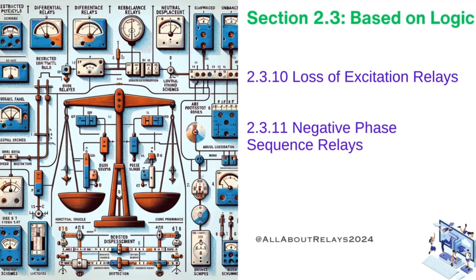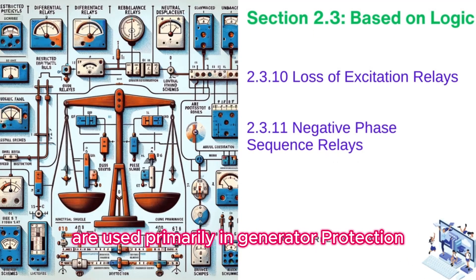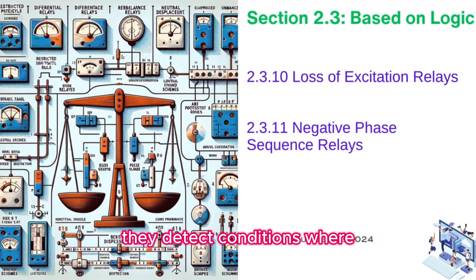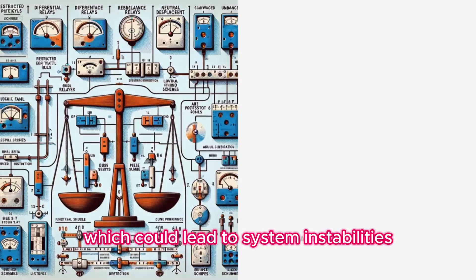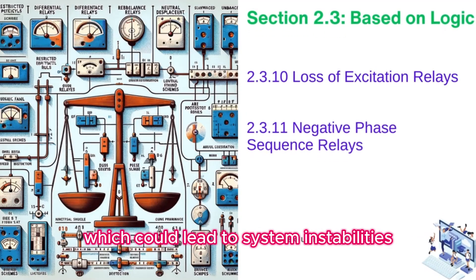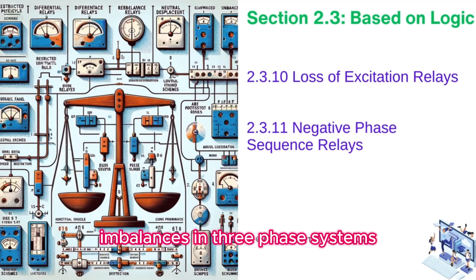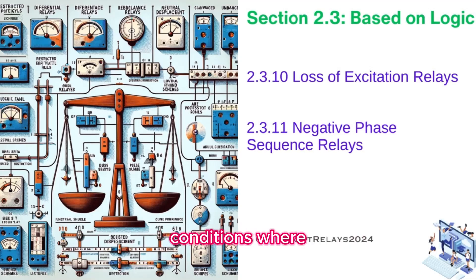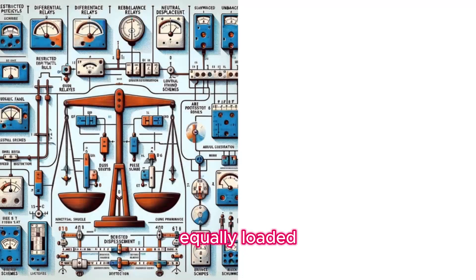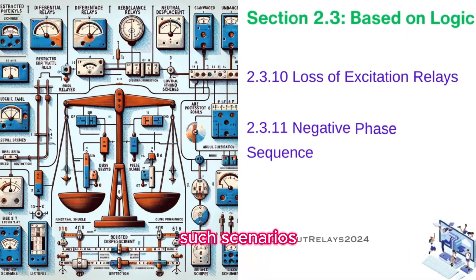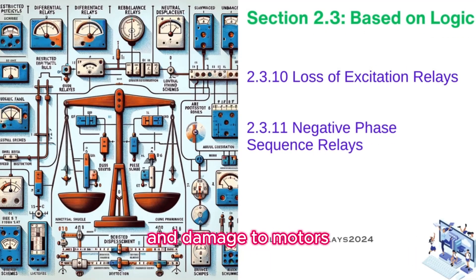Loss of excitation relays are used primarily in generator protection. They detect conditions where the generator loses its magnetic field, which could lead to system instabilities. Negative phase sequence relays identify imbalances in three-phase systems, specifically conditions where the phases are not equally loaded. Such scenarios can lead to overheating and damage to motors and generators.